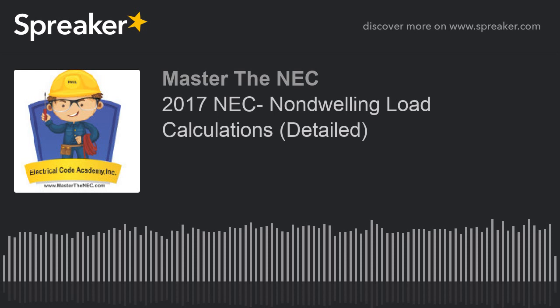Okay. Now, here in our calculations under 220.14(F), we're doing a calc. So we need to know what the minimum VA to use is in our calculation for each one of these required sign or outlining circuits when we're doing our load calculation for feeder or service. So in our case, it's a minimum of 1200 VA. Now, I'm going to remind you of something. If we have a sign or we have an outline system that has a nameplate with a VA value that is greater than 1200, then we have to use the greater value. This 1200 is just the minimum. This is the minimum if we didn't know any better. So we have to have at least 1200.